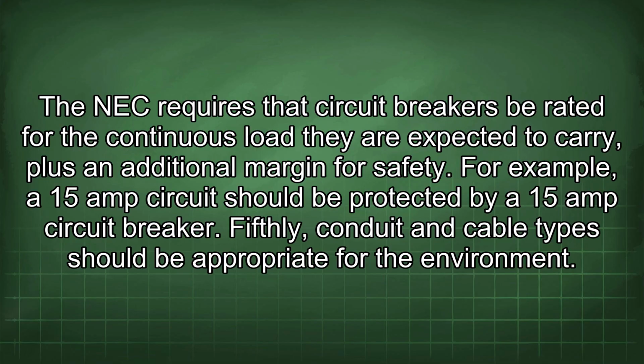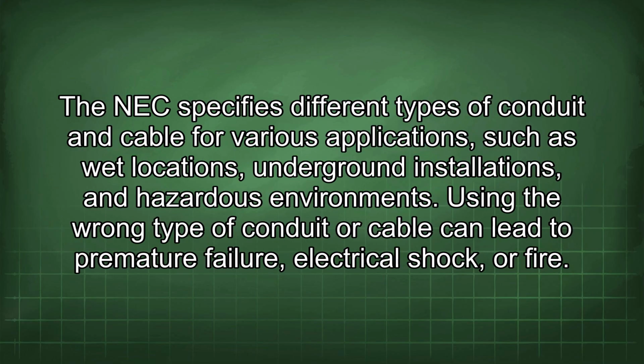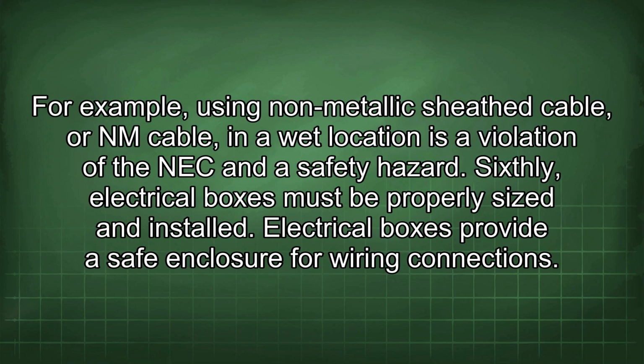Fifthly, conduit and cable type should be appropriate for the environment. The NEC specifies different types of conduit and cable for various applications, such as wet locations, underground installations, and hazardous environments. Using the wrong type of conduit or cable can lead to premature failure, electrical shock, or fire. For example, using non-metallic sheath cable, or NM cable, in a wet location is a violation of the NEC and a safety hazard.